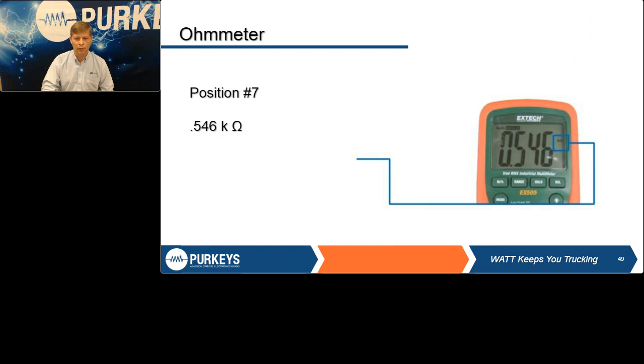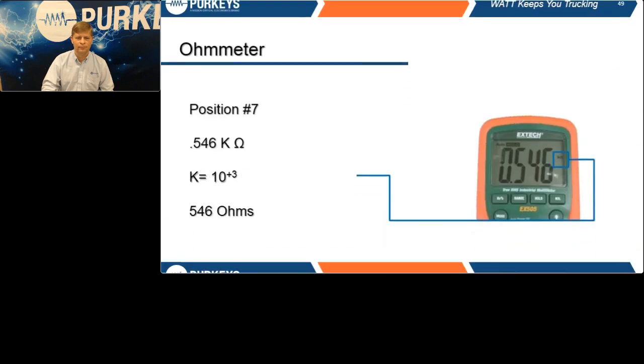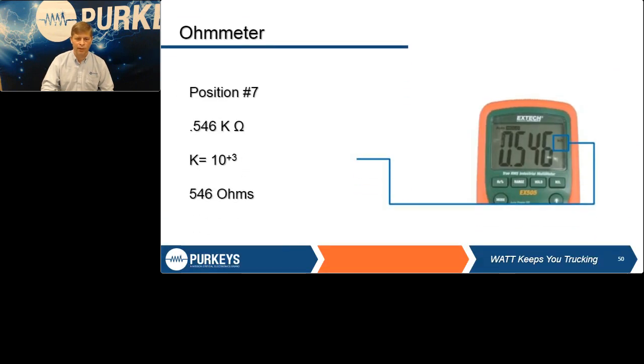Another one that causes trip ups at times is we have a 0.546K. How many ohms is that one? Actually, it's just 546. Most meters, if it goes over 500 ohms, move it to a K scale, which you'd think, why don't you just display 546? But again, that's the way most meters are.